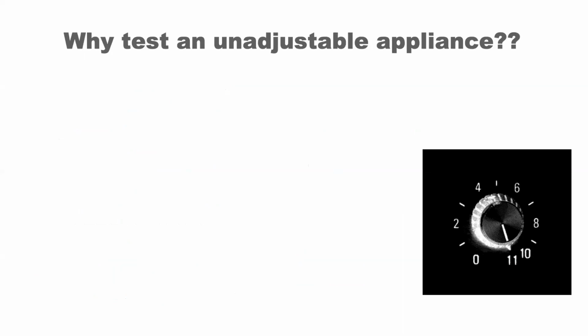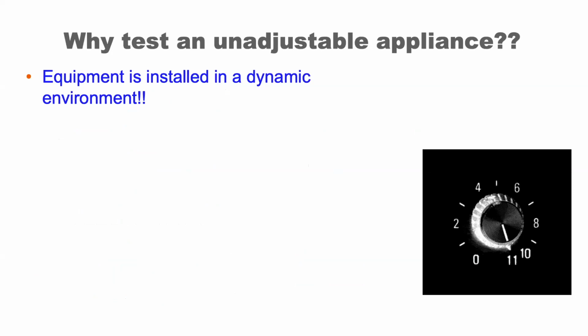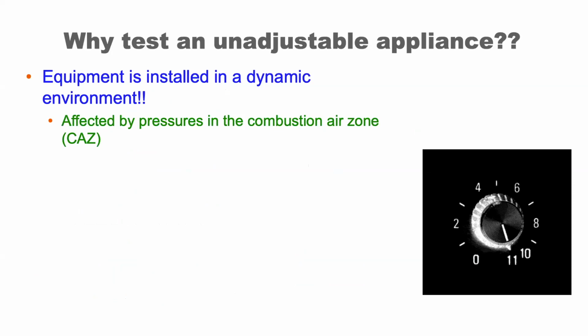So now, why would you test an unadjustable appliance, something that typically people think of as not being adjustable? Well, a lot of this has to do with the equipment being installed in a dynamic environment. And this is especially true for, we'll call it mid-efficiency to low-efficiency systems, which can be affected. The combustion air can be affected by pressures in the combustion air zone, the zone in which you're pulling the air from for combustion. Any system can be affected by fuel pressure or fuel quality.